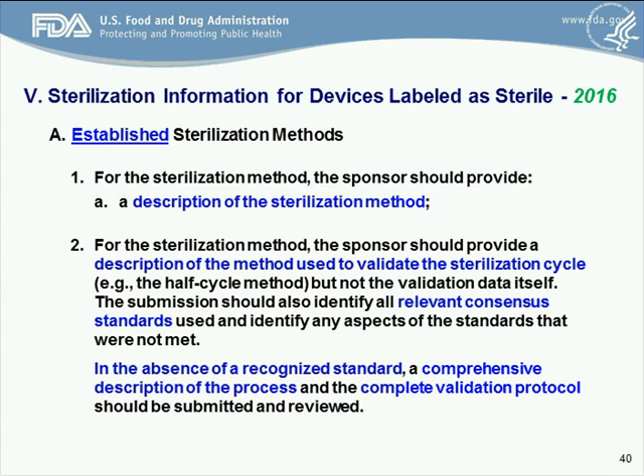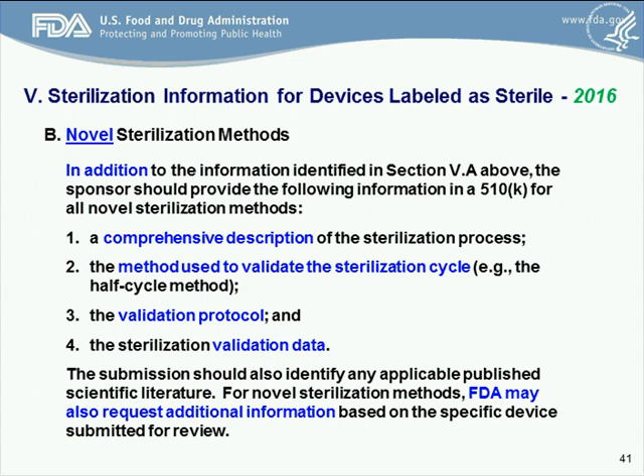Taking a look at the novel methods — you'll notice right off, this is in addition to all of the information documented in Section 5. We want to see that information, but in addition, we're looking for a comprehensive description of the sterilization process, the method used to validate the sterilization cycle, the validation protocol, as well as the validation data for the process. FDA may also request additional information based on the specific device submitted for review.